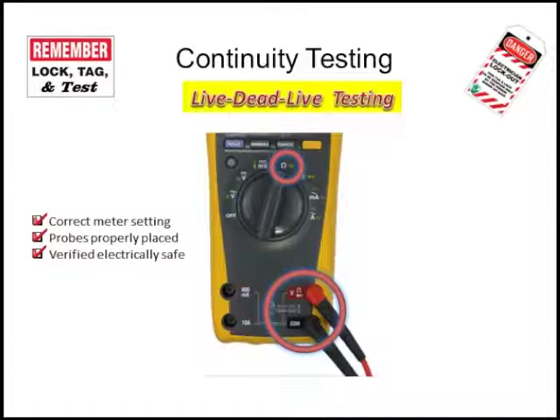Our final series of tests are going to be continuity testing or resistance testing. Now, in order to do this safely, we have to have locked, tagged, and tested the equipment first. We again call this live, dead, live testing. We want to make sure that our meter is on the correct settings, again, that our probes are properly placed, and that we have verified with a contact test that the system is electrically safe.